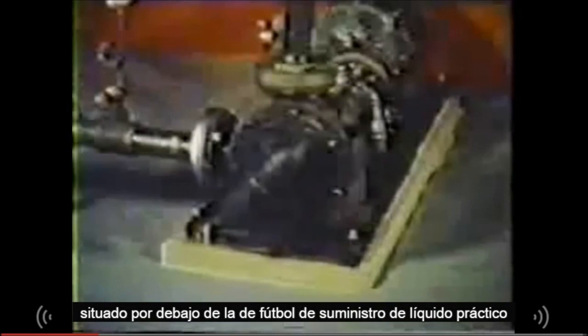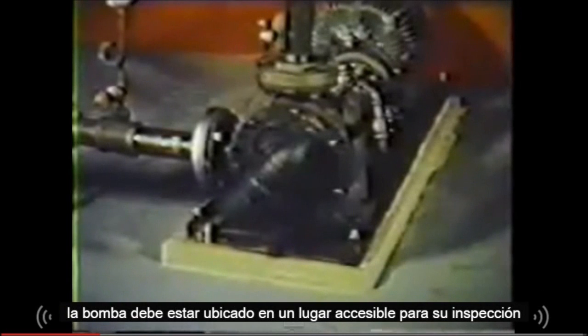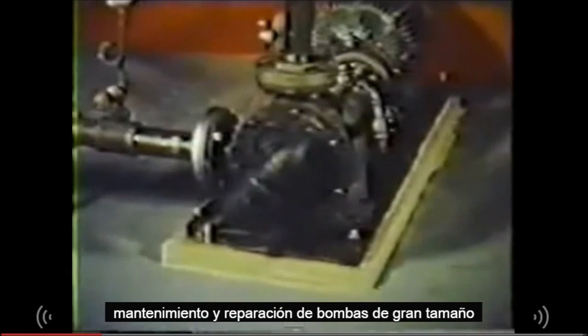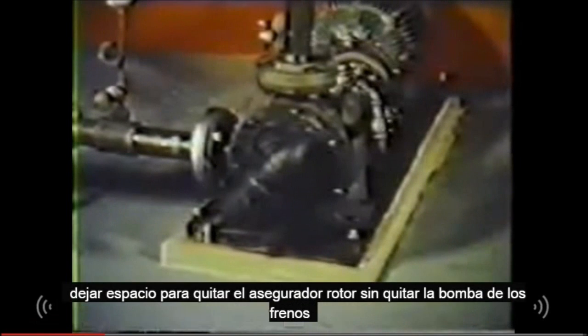Always locate the pump as close as possible to the supply of liquid to be pumped. Locate it below the liquid supply if at all practical. The pump should be located where it is accessible for inspection, maintenance, and repair. For large pumps, allow room to remove the rotor and shaft without removing the pump from the base.